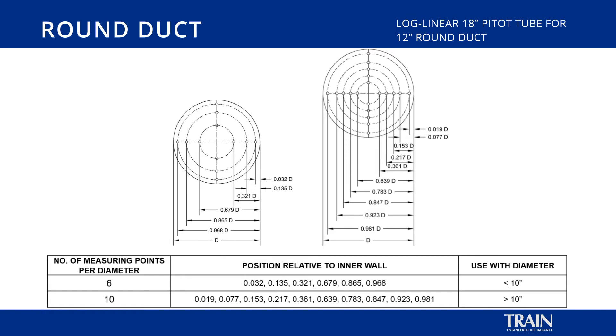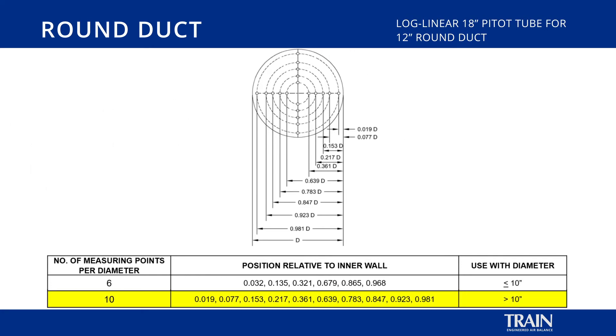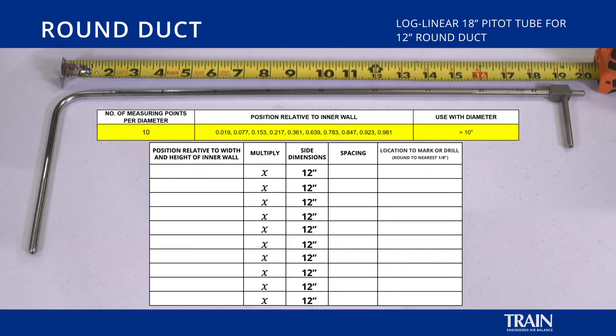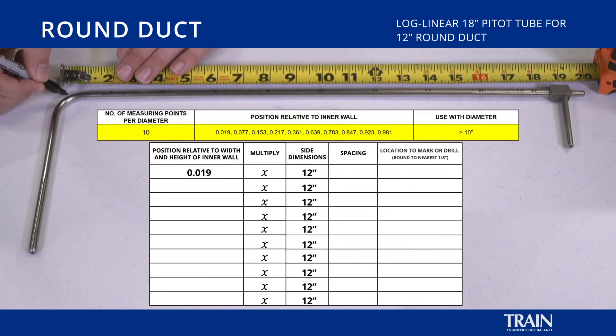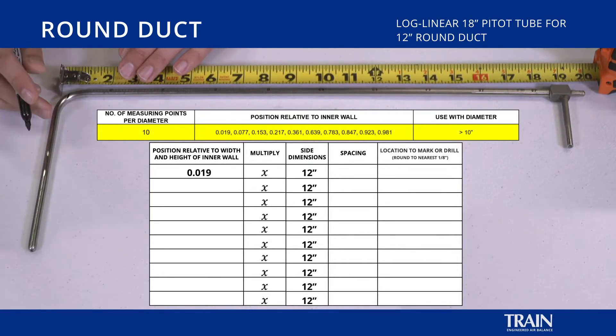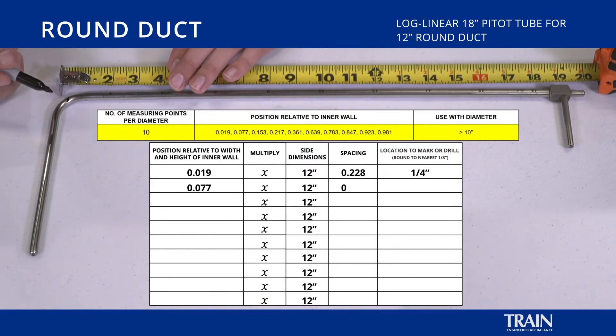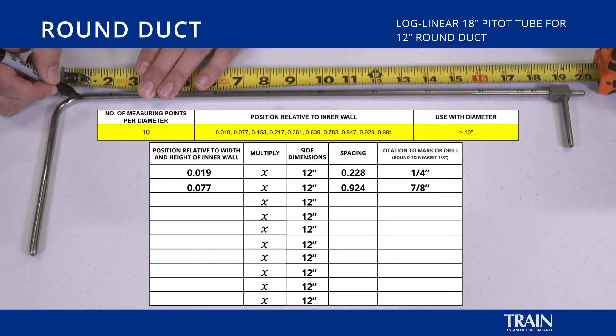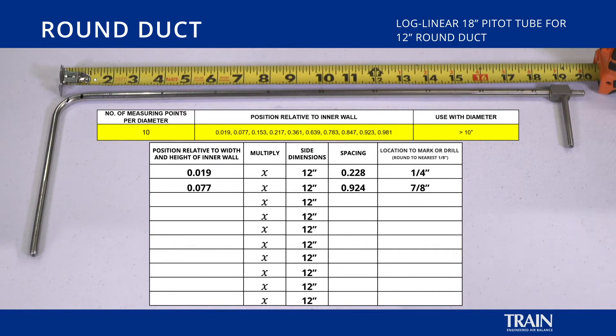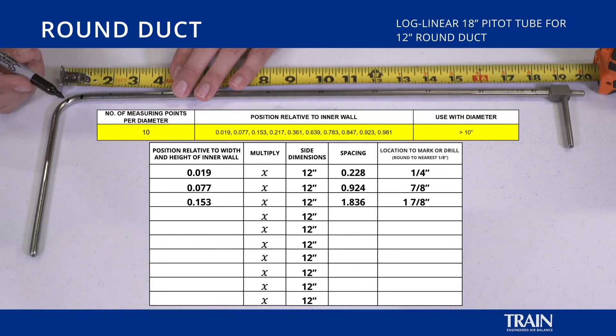For our next example, we will be performing a pitot tube traverse in a 12 inch circular duct. In order to mark our pitot tube for this traverse, we will be using the log linear chart and method, which indicates ten factors to multiply by the diameter of the ductwork. We begin with the first factor, 0.019 multiplied by our 12 inch round duct, which turns out to be a quarter of an inch. The next factor is 0.077, again multiplied by 12 inches, giving us 7 eighths of an inch. The third factor, 0.153, multiplied by 12 inches, results in a 1 and 7 eighths inch measurement.